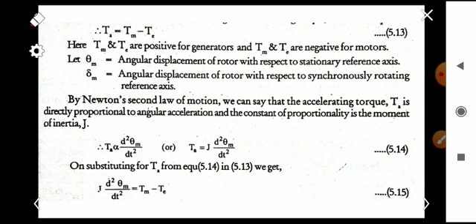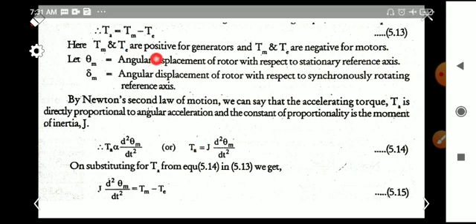T_M and T_E are positive for generators, and T_M and T_E are negative for motors. Here, theta_M is the angular displacement of the rotor with respect to a stationary reference axis, and delta_M is the angular displacement of the rotor with respect to a synchronously rotating reference axis. By applying Newton's law of motion, the net accelerating torque T_A is directly proportional to d²(theta_M)/dt², with proportionality constant J (moment of inertia, in kg·m²).